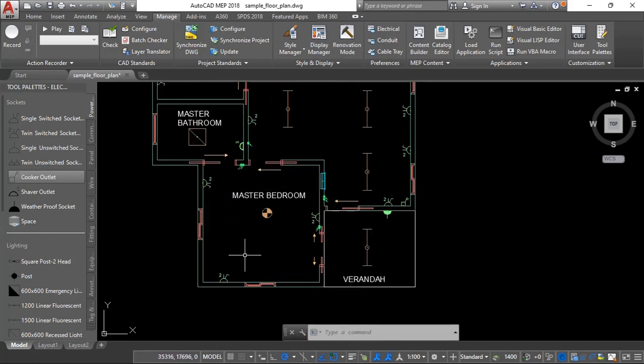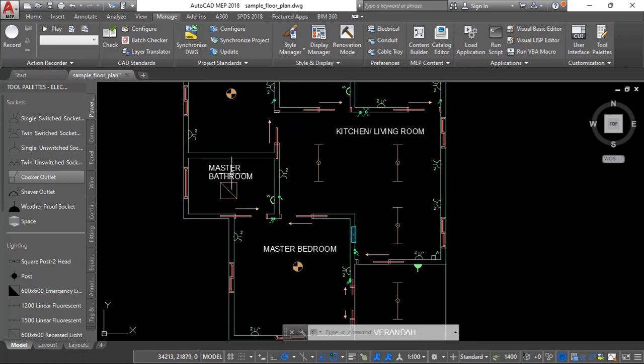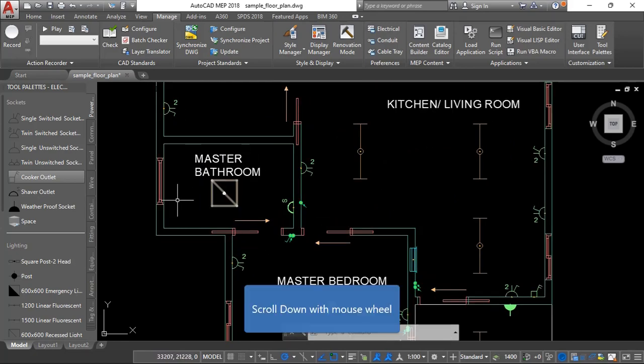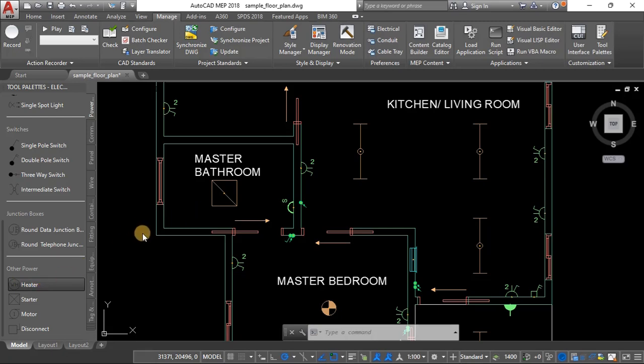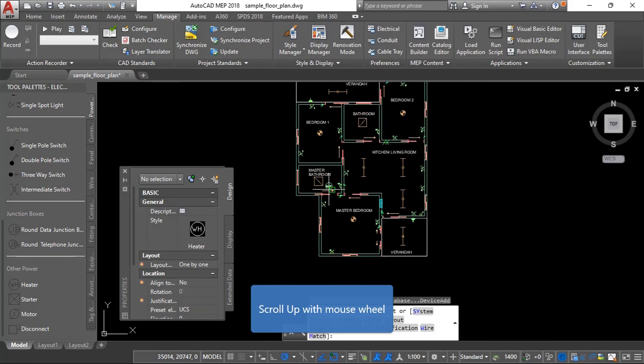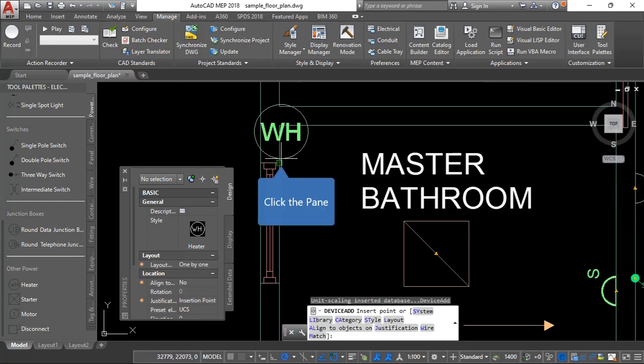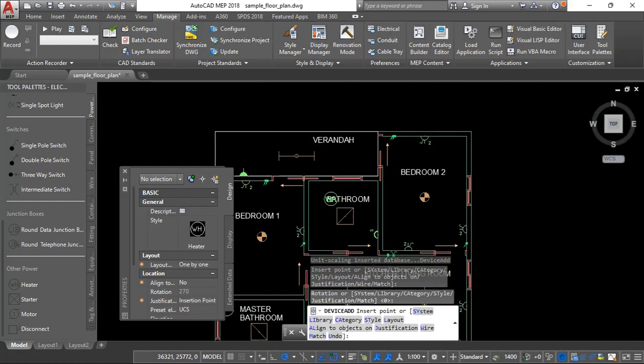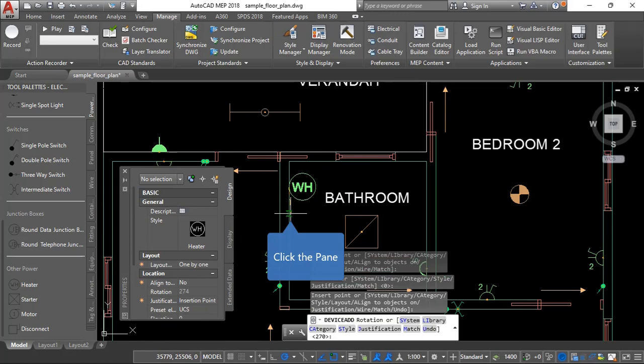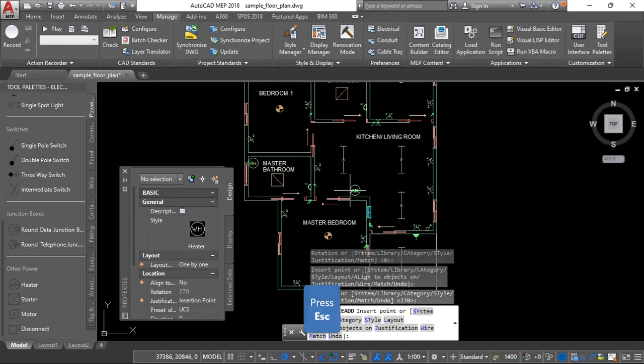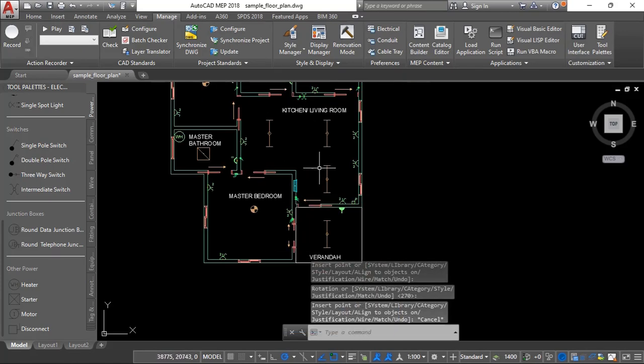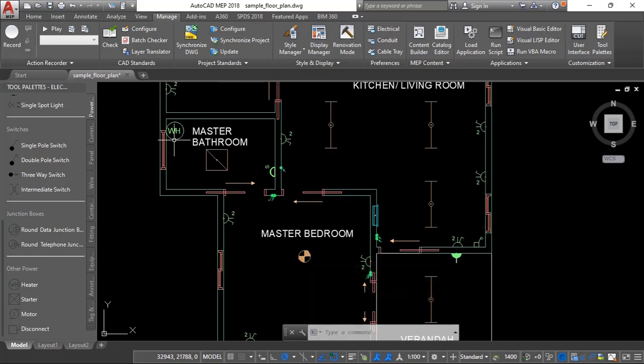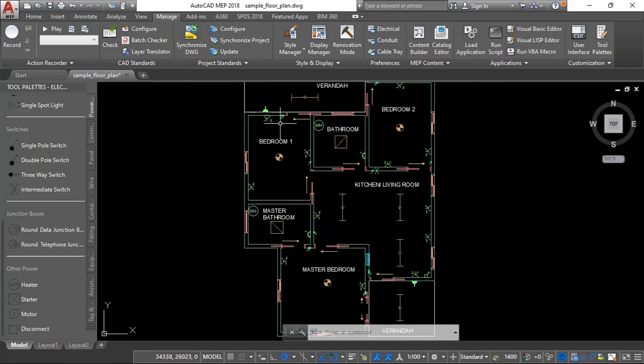Okay alright so we basically need one, two, then three, three circuits for the living room. Then we need one circuit for the bedroom. And also we need to add like a water heater, so I'll go ahead and add, there's water heater. Okay I'll put it somewhere here in the corner, and a water heater in this bathroom as well. Okay so that's going to increase our number of circuits. So so far we have three, four, the water heater should have a separate circuit so that is five, and the bathroom should have its own circuit for the light and shower unit, so those are six.